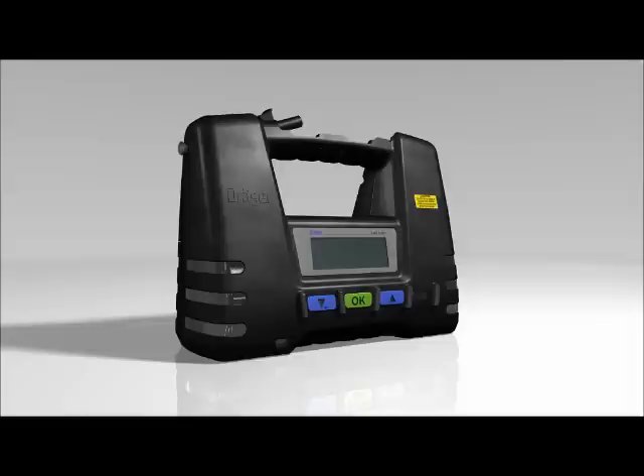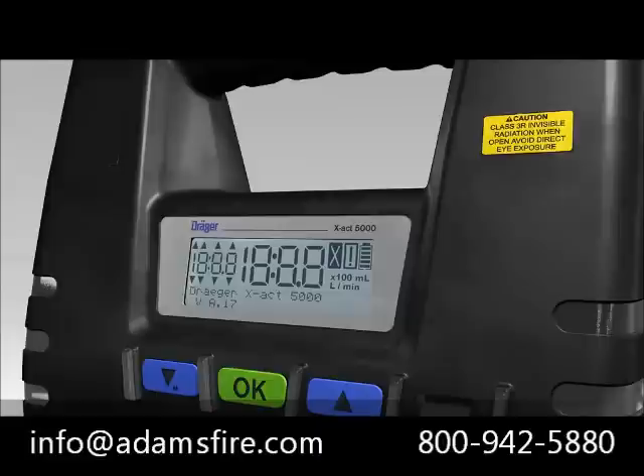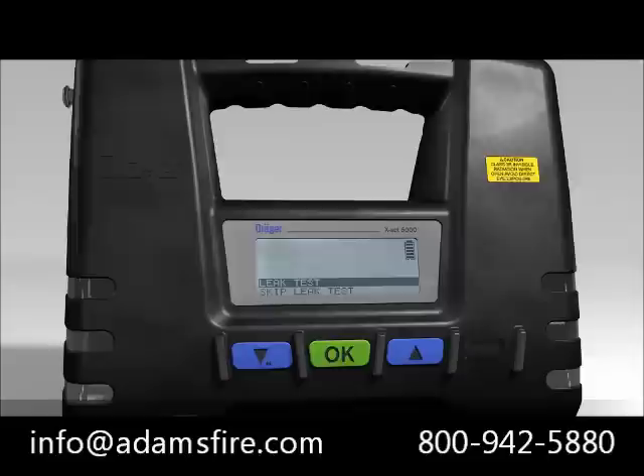Turn on the tube pump using the OK button. Keep the OK button pressed until the tube pump counts down from 3 to 1. Once the screen appears, the tube pump is switched on. The Dräger X-act 5000 will now perform a self-test routine. After turning on, the message LEAK TEST or SKIP LEAK TEST always appears in the display.